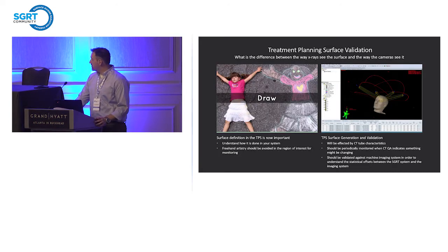The treatment planning system is one that gets overlooked a lot. You need to understand the difference between your DICOM RT surface and your camera-perceived surface. The camera works by viewing reflected pseudo-random dot patterns of light back to the camera sensor — a different modality than thresholding CT attenuation through the patient surface. That thresholding will change as your CT gets older, as tube fatigue changes the spectrum and your DICOM surface shifts. We track this once a year as part of our annual QA and you can actually see a statistical offset grow between your DICOM surface and your optical surface — something you should track, especially for SRS.